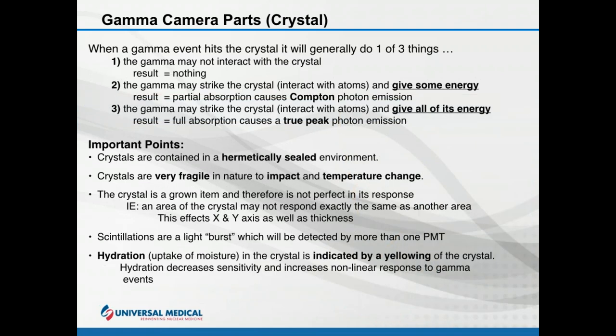When a gamma ray strikes a crystal it can do one of three things: it may pass right through with no interaction and no scintillation; it may interact and give off only some energy, producing a partial absorption and contributing to the Compton peak; or it may interact with atoms and give all of its energy to the crystal, creating a true energy response — a true scintillation — which gives us a true photo peak for emissions.